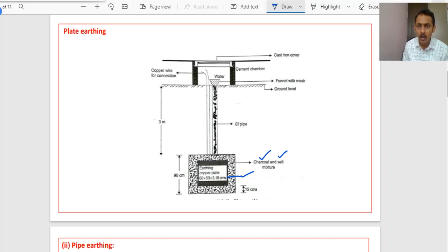This earth plate should be surrounded with the help of this charcoal mixture. All these arrangements are made in order to bring the resistance as low as possible, so that we provide a high conducting path through the earth wire. If the resistance offered by the earth wire is more, it cannot give you proper protection. The resistance offered by the earthing system should be as low as possible.